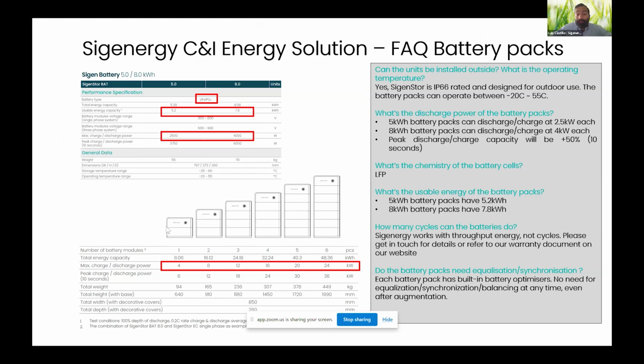Now, when you charge directly from the PV modules, if you have on that 5 kilowatt inverter 8 or more kilowatts of DC power, that can go directly to the battery without being limited by the energy controller, because the inverter circuit doesn't participate in the operation. So this is the advantage of a DC coupled solution like ours.